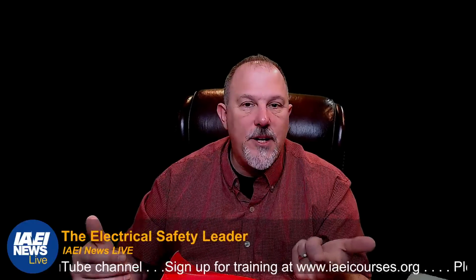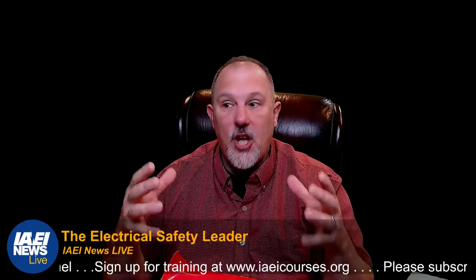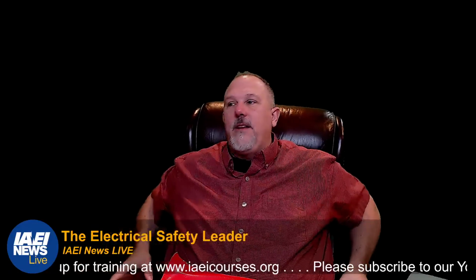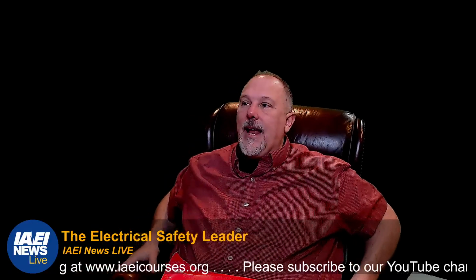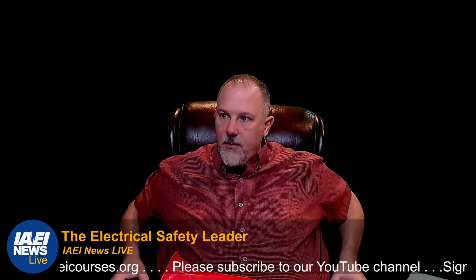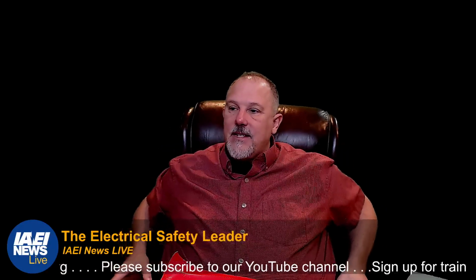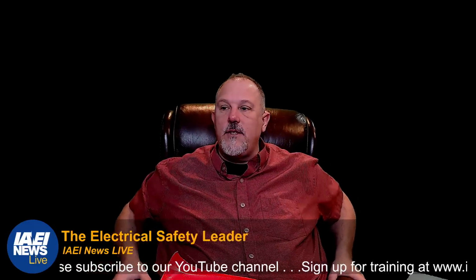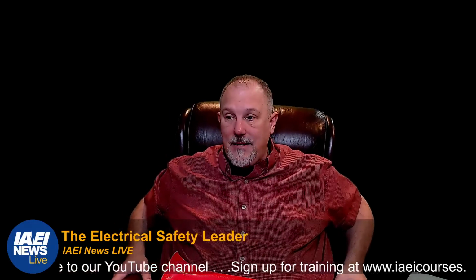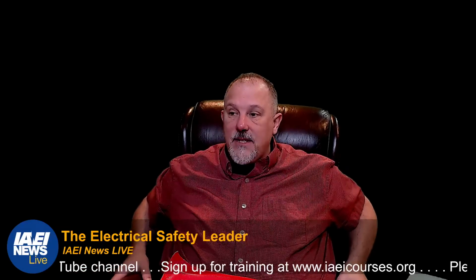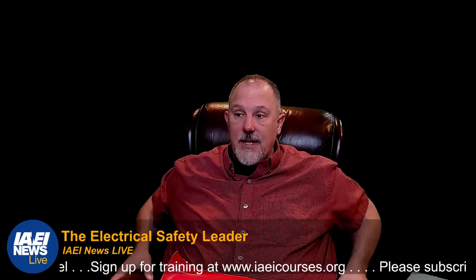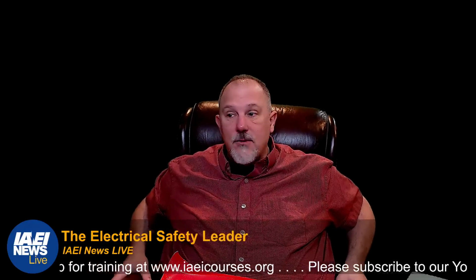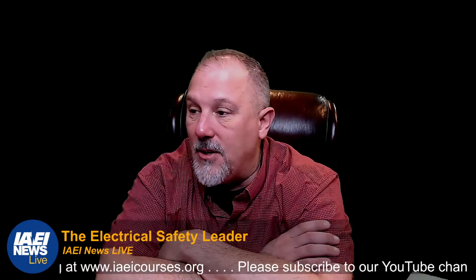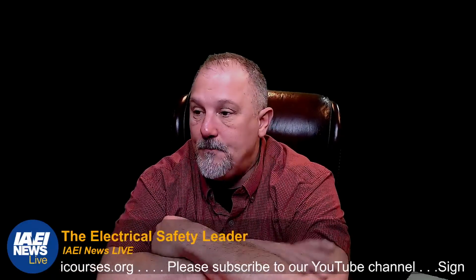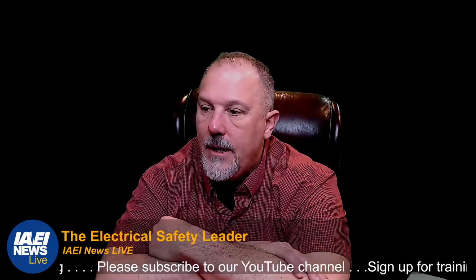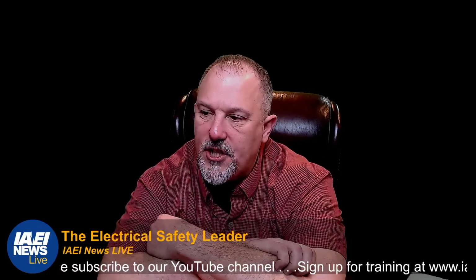Verify instrument transformer ratio. So if there are CTs in that enclosed panel board, and I'm having a problem with the word panel board, we're going to have to say enclosed panel boards and switchboards. I really do believe so. Inspect insulators for damage or contaminated surfaces. Verify filters are clean and in place. You've got to ensure maintenance devices and tools are available for equipment servicing. You have to verify any barriers are in place. Visually inspect the environmental controls that are provided, if there are any. And then for individual components, refer to the appropriate chapters of the standard.